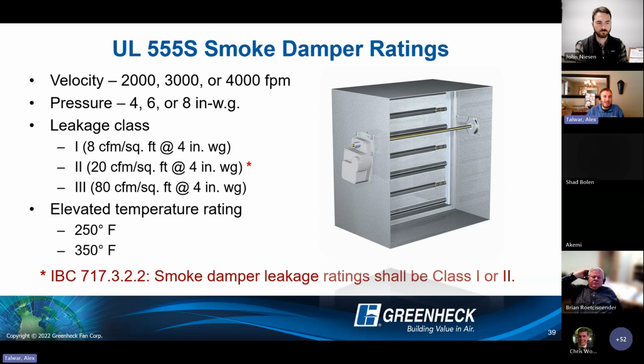Class 1 means you're allowed 8 CFM of leakage per square foot of damper area at a 4-inch test pressure. It's actually 4.5 inches. We're always bumping up the test and velocity pressure for a safety factor. I'll go a little more into what that means a little bit deeper on the next slide.